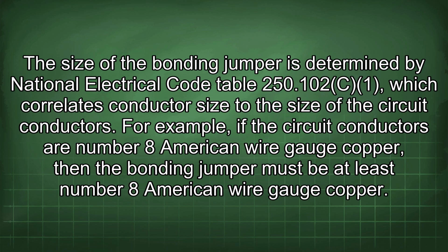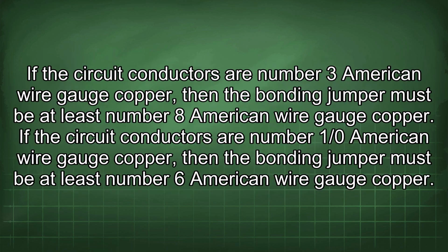For example, if the circuit conductors are number 8 American wire gauge copper, then the bonding jumper must be at least number 8 American wire gauge copper. If the circuit conductors are number 3 American wire gauge copper, then the bonding jumper must be at least number 8 American wire gauge copper. If the circuit conductors are number 1/0 American wire gauge copper, then the bonding jumper must be at least number 6 American wire gauge copper.